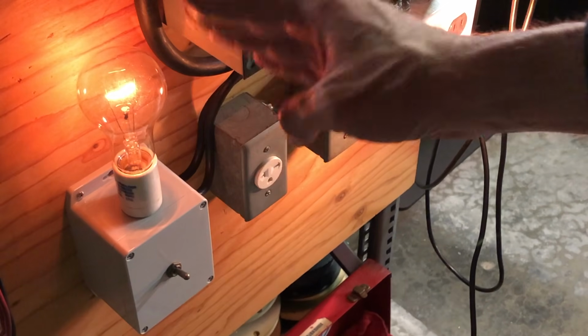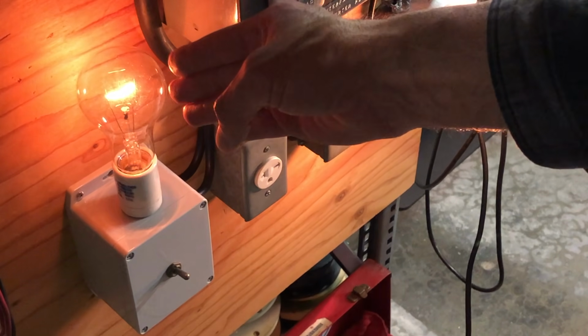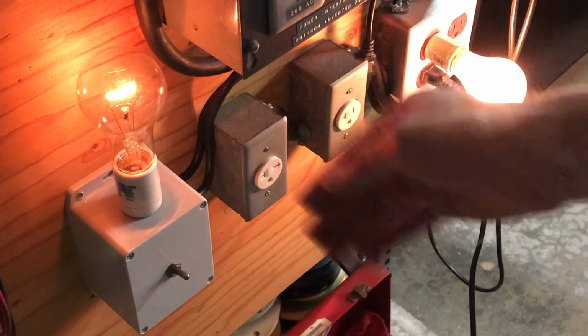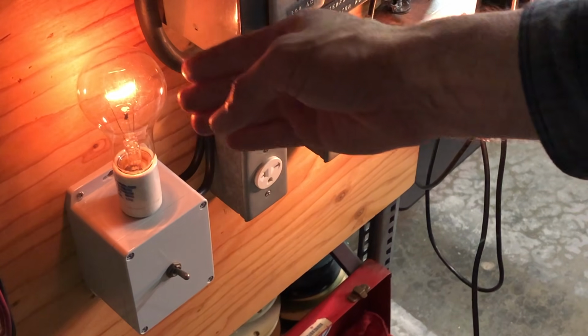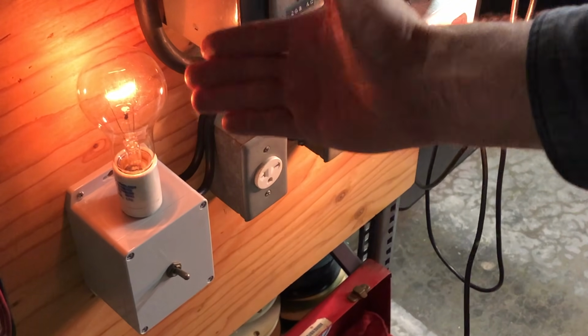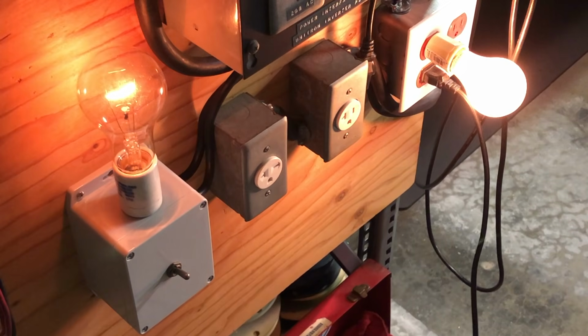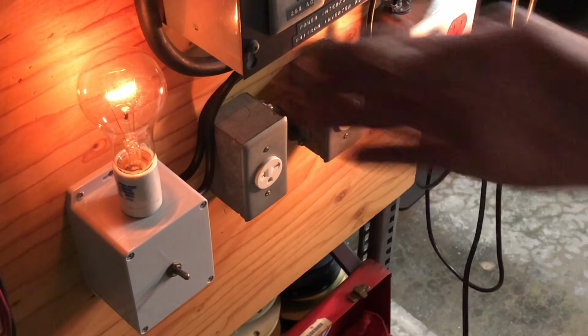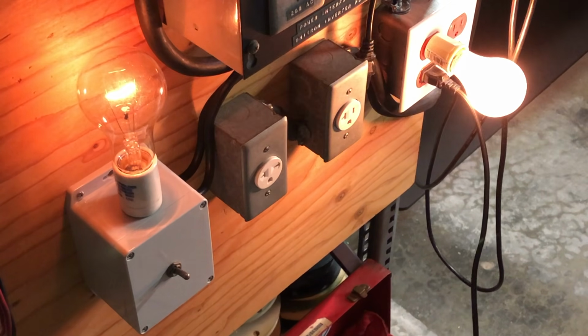So if you wanted a lot of current limiting, use say a 25 watt bulb, a 60 watt bulb, something like that. This is 150 watts. You could use 200 watt. I have a 300 watt bulb that I can install in here for something that's larger and requires more current just to operate normally. But again, even with a 300 watt bulb, if there's a direct short, you would have nowhere near the current flow that you would if you had no limiting whatsoever through the bulb.